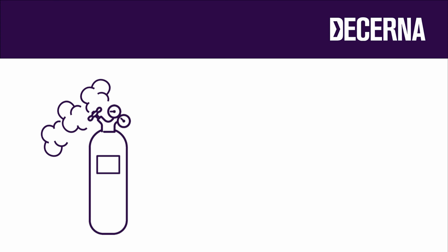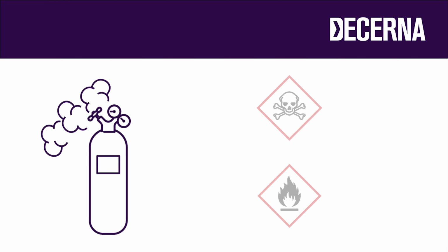The most damaging of these refrigerants are being withdrawn and phased out in favour of some with a lower GWP. A refrigerant called R32 has become a popular alternative, but this still has a GWP of 700. Some systems use natural refrigerants such as ammonia, and these have a much lower GWP, but they still have to be carefully managed due to their flammability and toxicity.